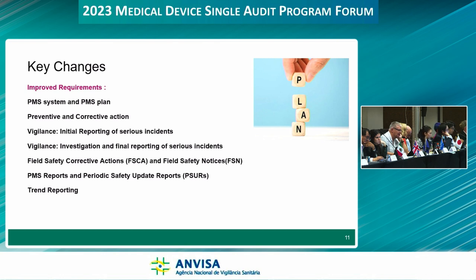I'm not going to go into detail in this because I'm not an expert in this particular area, but there will be improved requirements on the PMS system and PMS plan, further regulations on preventive and corrective action, vigilance reporting to bring it more in line with reporting timelines in Europe, more information on how field safety corrective actions and field safety notices should be produced, and PMS reports and periodic safety update reporting. For higher risk devices, we'll want more frequent feedback on PSURs.